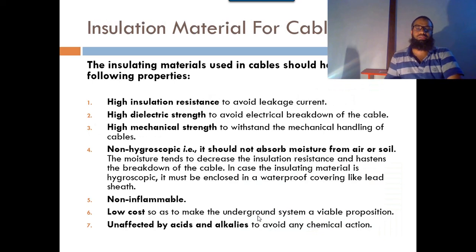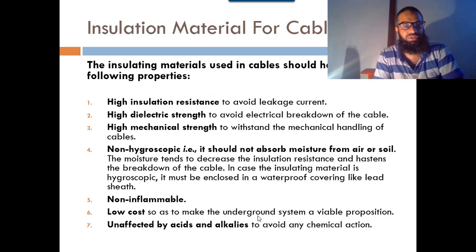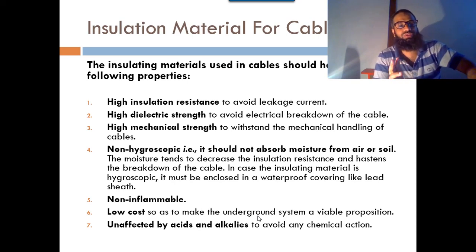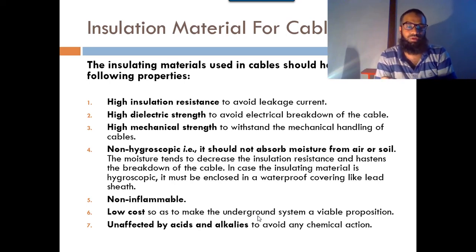So these are some important things which are required in underground cables, like the quality of the cables. First, its insulation resistance should be very high in order to avoid leakage current. Secondly, its dielectric strength should also be very high in order to avoid the electrical breakdown of the cable. Third one is high mechanical strength to withstand the mechanical handling of the cable. Fourth one is non-hygroscopic. It means that it does not absorb moisture or air from the soil.